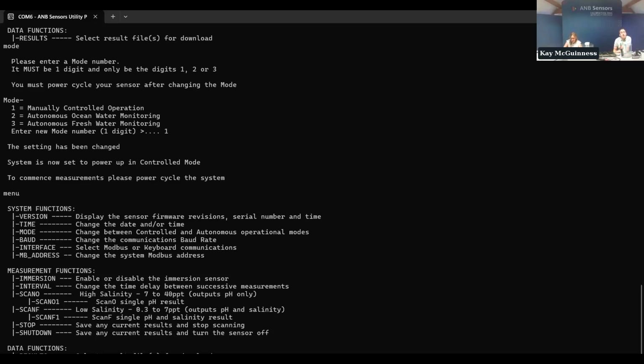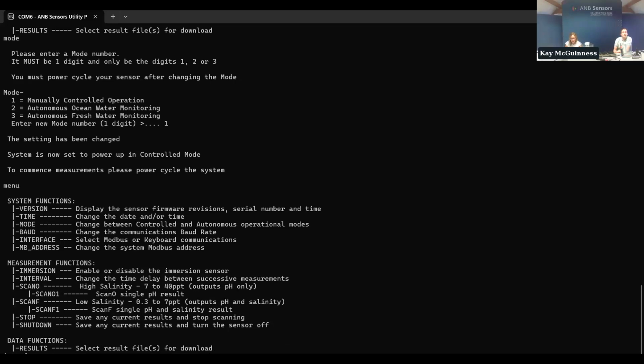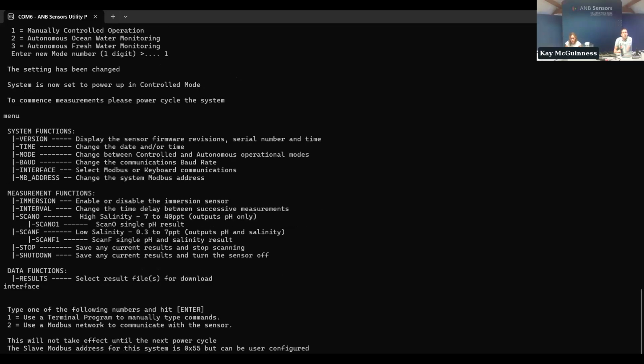Perfect. So the next one is interface. If we type interface, it allows you to change between Modbus communications or keyboard communications. So Modbus, all the commands for the Modbus are on our website. These follow the same command structure as the terminal mode. So you can send scan commands, or you can do read pH commands through the Modbus menu. It's been integrated now onto a number of Modbus 232/485 platforms, and so it's quite smooth and easy. And we did a lot of work at the start of the year in making this better, and now it's very stable and robust. Any questions, please feel free to reach out to us, but it's working well.